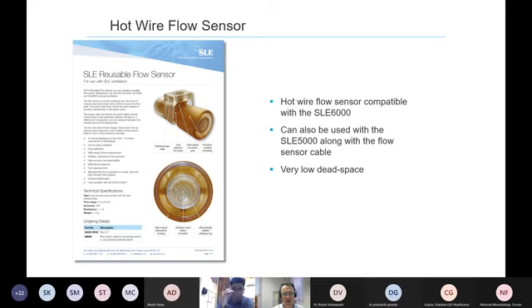The flow sensor has a piece of platinum wire inside it, which is what makes them rather expensive. And it's the platinum wire which senses very small changes in flow of gas, either into or outside the flow sensor. So this technological step allowed us to start measuring very small volumes and very small flows proximally to the patient. These flows or changes in volume used to be measured at the ventilator, which was some great distance away from the infant. So small volumes were either missed or couldn't be measured, and breathing efforts from babies were also missed as well.